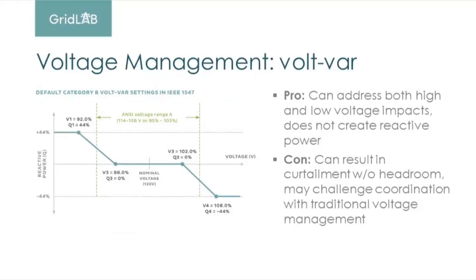So first, let's talk about volt-var. I'm showing the voltage curve here, and this is the standard. This is the category B volt-var setting for IEEE 1547. One of the great things about volt-var is that it responds to the voltage on the circuit. So the smart inverter, based on what the voltage is doing on the circuit, will either be absorbing or generating reactive power to try and help either increase or decrease the voltage on the circuit. You can see that there's a dead band between 98% and 102% of nominal voltage. The inverter isn't going to do anything with reactive power there, but above that, it's going to start either producing or absorbing reactive power, up to 44% of its capabilities, about 0.9 power factor, until it hits either 92% or 108%, at which point it's not going to keep increasing its reactive power. So it has some limits, right?